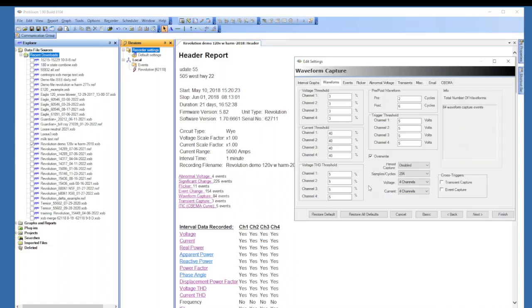Waveform capture. Typically, I choose to uncheck the override box there. Sometimes when you're removing a recording, it bounces, and good waveforms could get overwritten. So this is a snapshot of 9 cycles. You have 2 cycles, then you have the trigger cycle, and you have 6 more cycles. You can adjust these, so if you really want 60 cycles in a waveform capture, you can, but you do have fewer waveforms, and you are limited to waveforms.